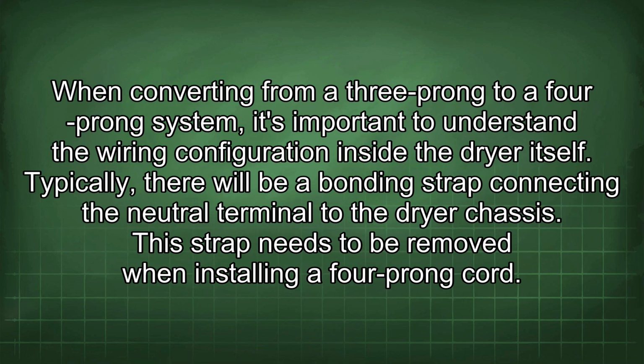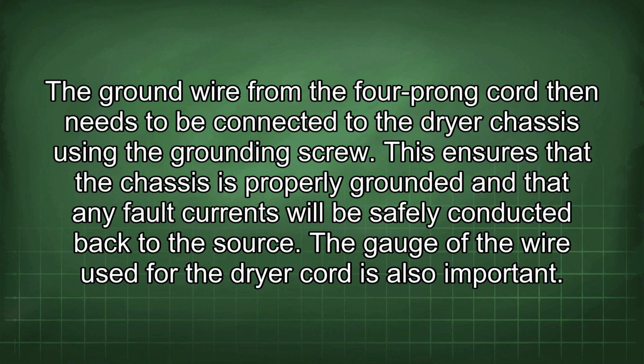When converting from a three-prong to a four-prong system, it's important to understand the wiring configuration inside the dryer itself. Typically, there will be a bonding strap connecting the neutral terminal to the dryer chassis. This strap needs to be removed when installing a four-prong cord. The ground wire from the four-prong cord then needs to be connected to the dryer chassis using the grounding screw. This ensures that the chassis is properly grounded and that any fault currents will be safely conducted back to the source. The gauge of the wire used for the dryer cord is also important.